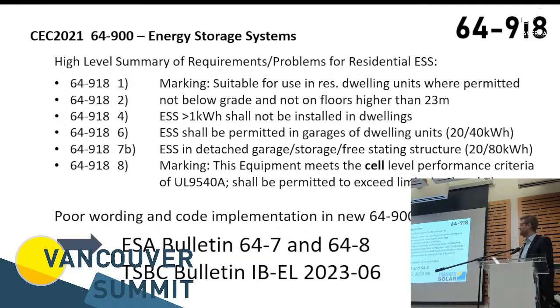So the most critical part is section 64.900, more specifically 64.918. And let's go through what the code actually requires. It needs to be marked suitable for use in residential dwellings where permitted. First thing is, no battery system currently on the market has that labeling because none of them is passing under that cell performance level criteria. Then the other thing is, it cannot be below grade and cannot be on floors higher than 23 meters. So most people have space typically in their basement, but unfortunately that is, if we read the code, off the radar. The energy storage systems cannot be larger than 1 kilowatt hour.